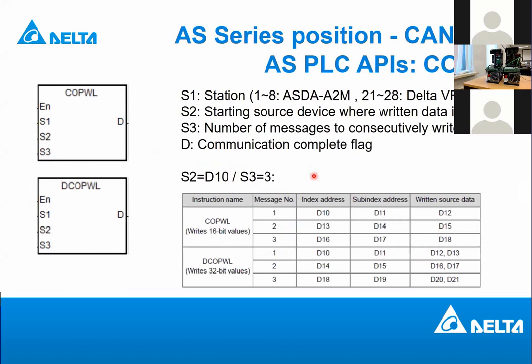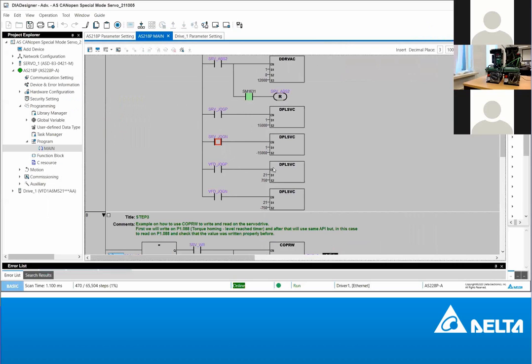So let's go to that. Let's test for the inverter. So if everything is okay, we should see our inverter running. So now the station address is 21. You see, it's the same thing we use for the servo drive, DPLSVC, velocity movement, speed movement. This is for the station address of the inverter. So let's trigger this. You should see my inverter. It should be running using this RPM that is stipulated here. True. Perfect. You can see in the video, the inverter is running.